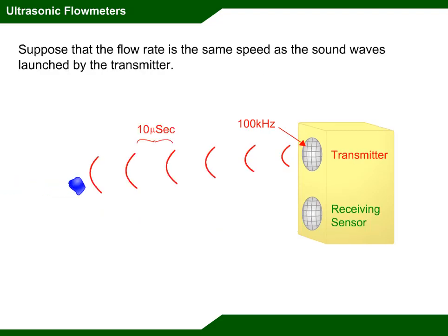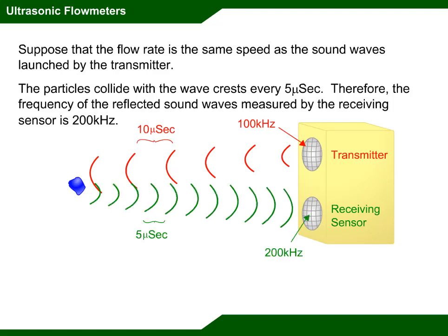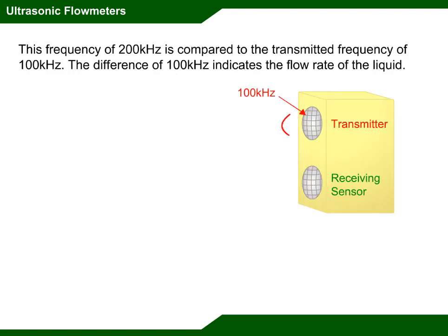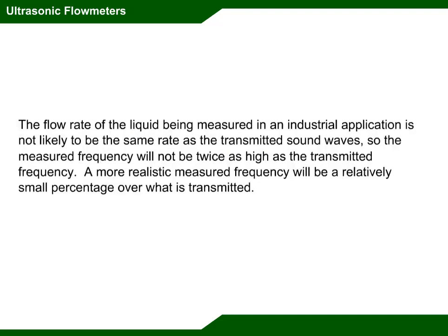Suppose that the flow rate is the same speed as the sound waves launched by the transmitter. The particles collide with the wave crests every 5 microseconds; therefore, the frequency of the reflected sound waves measured by the receiving sensor is 200 kilohertz. This frequency of 200 kilohertz is compared to the transmitted frequency of 100 kilohertz. The difference of 100 kilohertz indicates the flow rate of the liquid. In a realistic industrial application, the measured frequency will be a relatively small percentage over what is transmitted.